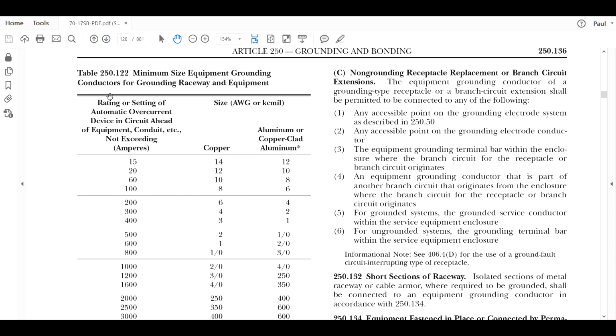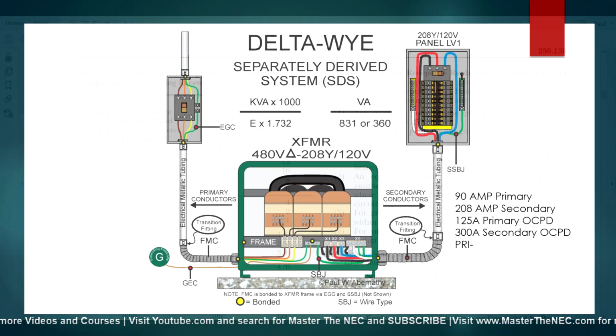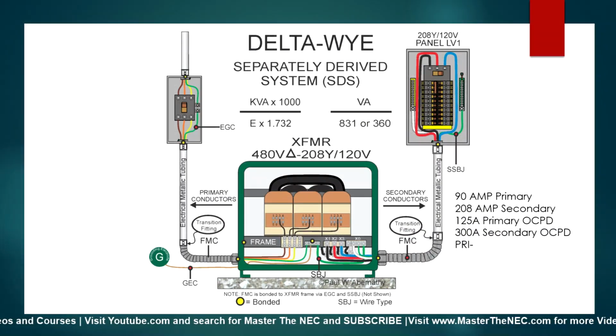Okay, so 250.122, based on the overcurrent device ahead of it, we said it was 125. It falls between 100 and 200, so we're going to use the 200, because obviously it's not 100 or less, so we can't use that. So it's going to be a 6. In this application, this equipment grounding conductor is going to be a 6. So we've got 2 gauge conductors and a 6 gauge equipment grounding conductor. So we're done there. Now let's do this supply side bonding jumper.